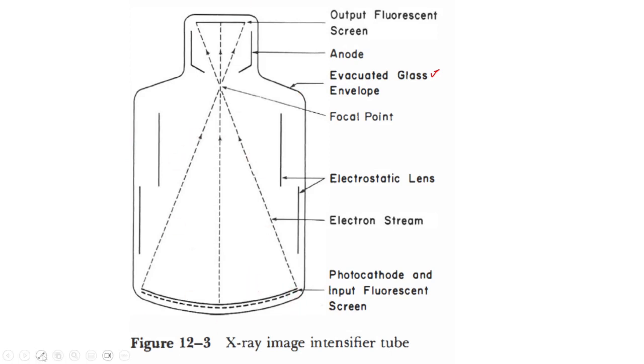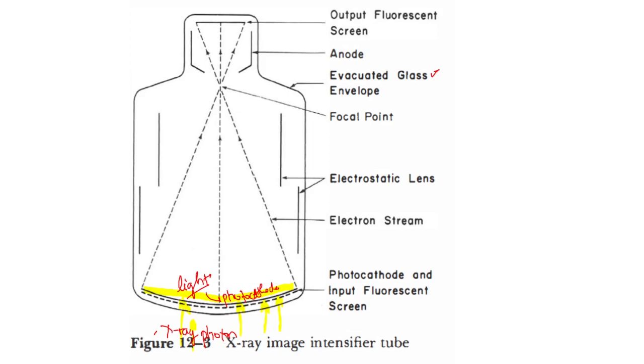The X-ray beam enters the image intensifier tube. The input fluorescent screen absorbs the X-rays. The X-ray photon energy is converted to light energy — the input phosphor absorbs the X-rays and converts them into light. This light then strikes the photocathode, which produces photoelectrons.